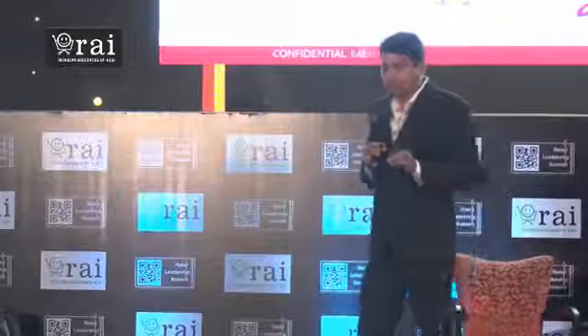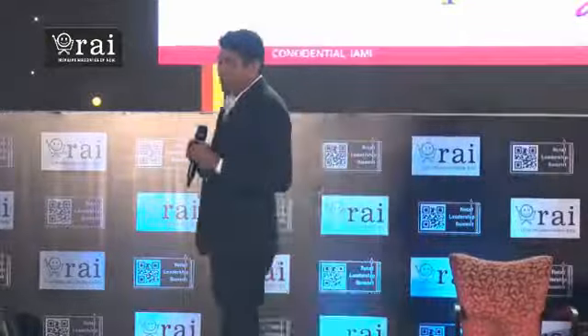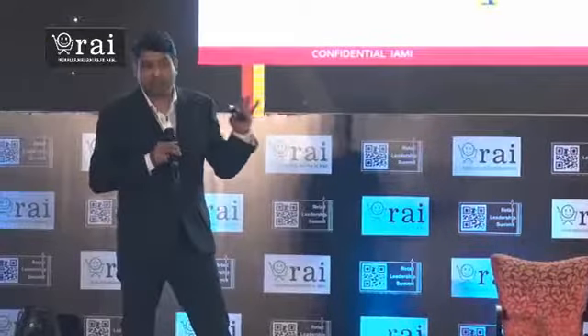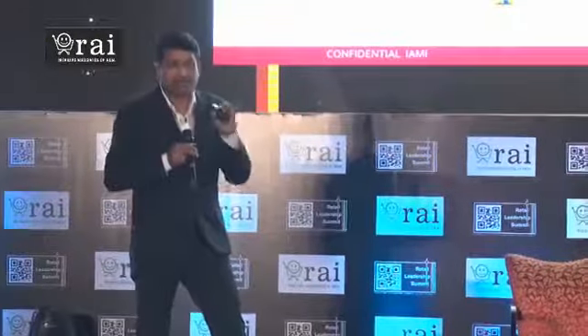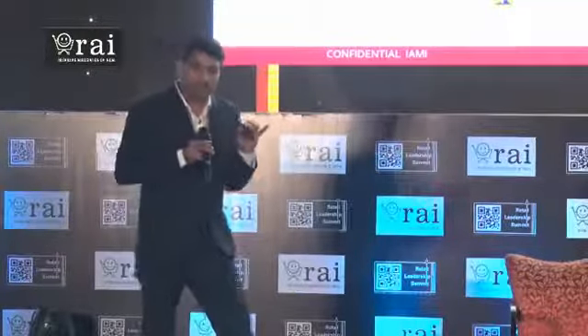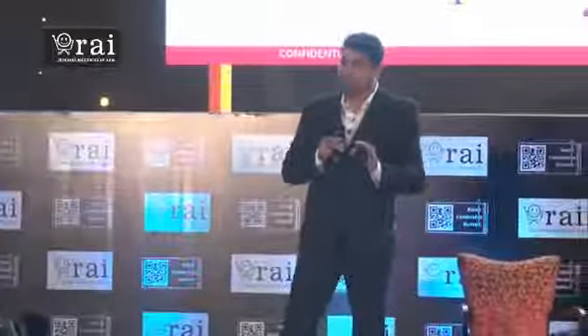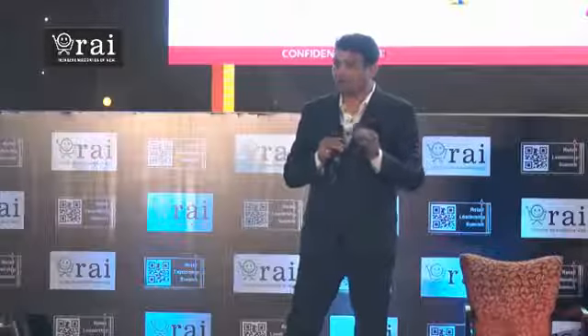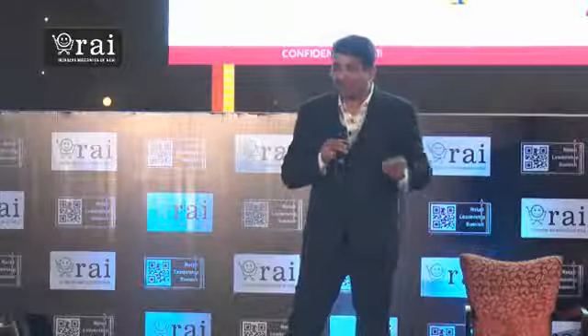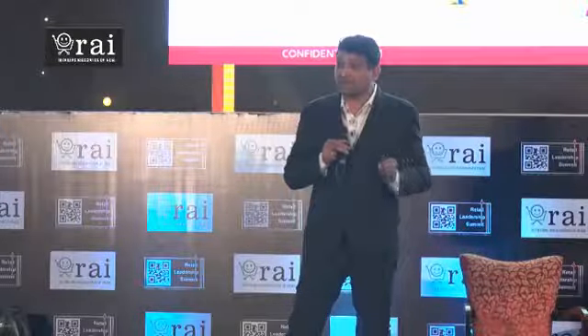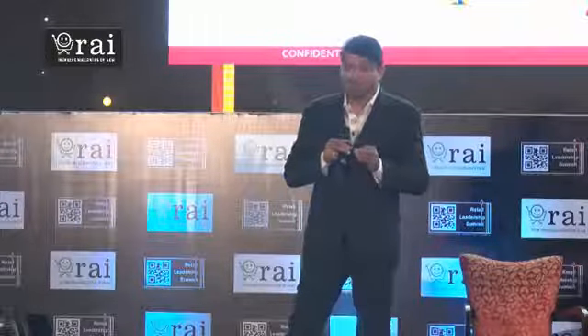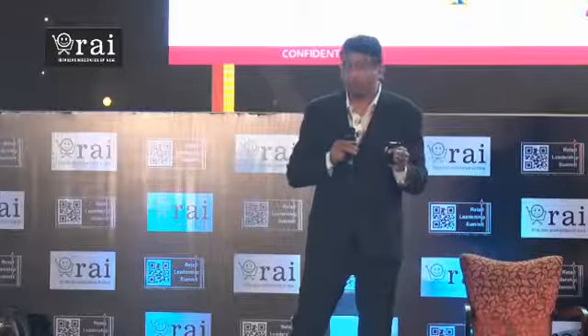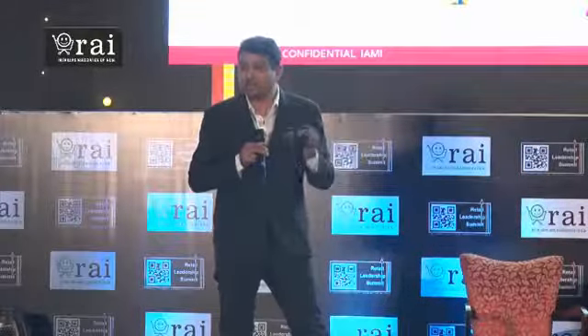A simple example from the ICICI case: the hoarding light at the front is controlled by a simple timer. In the evening at 7 o'clock it starts, and around 2 o'clock at night it switches off, because after 1 or 2 o'clock nobody is going to use it. By doing this across all branches, they saved 5% of the energy. 5% across, say, 4,000 to 5,000 branches is a big value. So just by saving energy, you can earn.